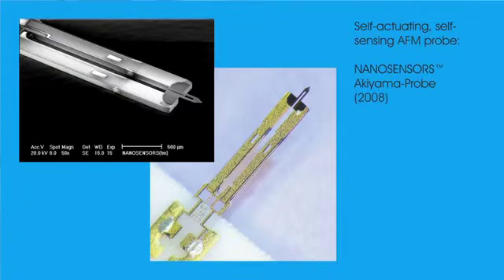The Akiyama probe, the brainchild of Dr. Akiyama, arrived in 2008 and uses an oscillating tuning fork to manipulate the cantilever and to monitor the interaction between the tip and the surface. A true self-sensing probe, no longer requiring the input signal from a beam deflection laser, this probe allows the construction of extremely compact and easy to transport AFMs.